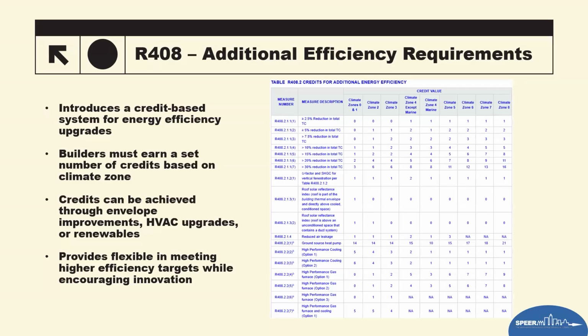So each measure is assigned point values per the climate zone, and the number of credits is dependent on the climate zone that you're in. And this approach promotes cost-effective compliance and rewards builders for integrating high-performance features into their home. So if you have a home that's built as standard construction today and it's R13, but you've made a choice to go with a 90-plus AFUE furnace or a high SEER equipment because you're marketing yourself as a very high efficiency builder, well, then this allows you to actually take credit for that.